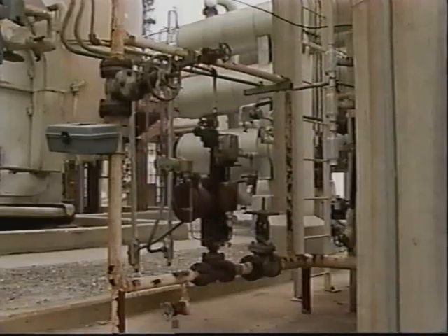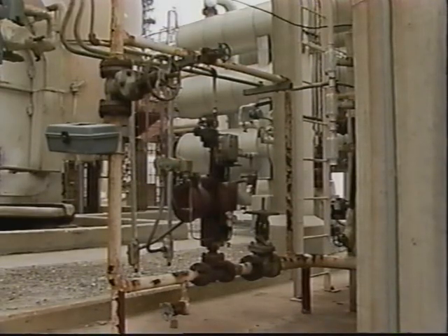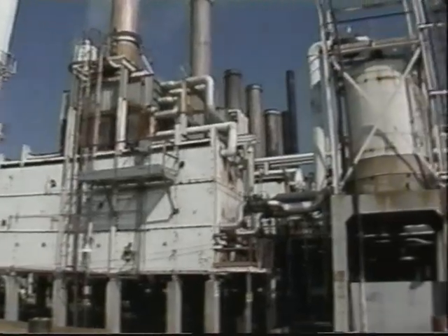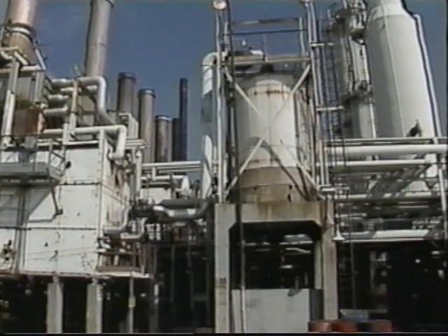Control systems differ, and so do the operating procedures associated with them. When troubleshooting control systems, you'll need to follow your facility's procedures to make sure you proceed safely. The example we'll look at here is a control system that regulates a furnace's outlet temperature. This furnace heats a process fluid for a reactor. The outlet temperature of the process fluid is controlled by regulating fuel flow to the furnace.